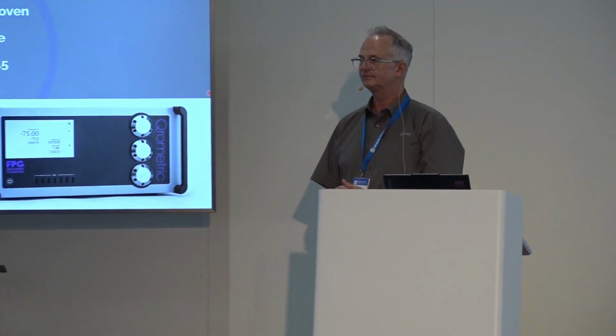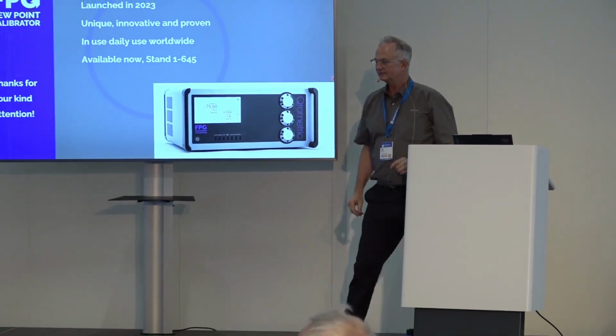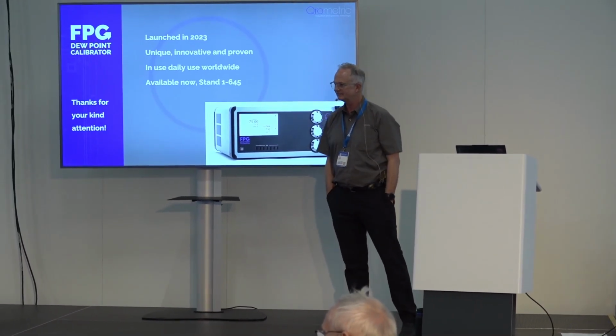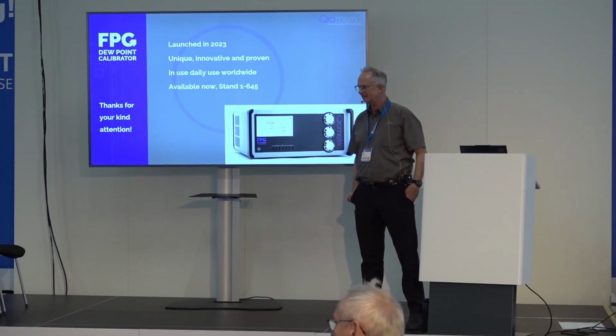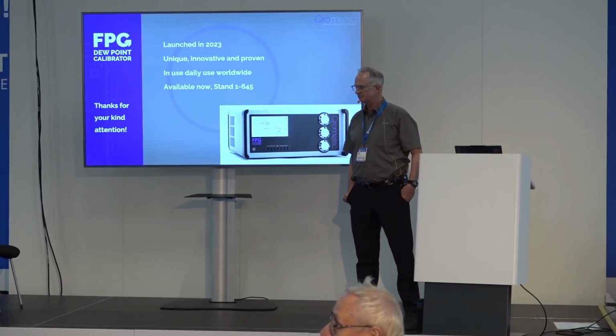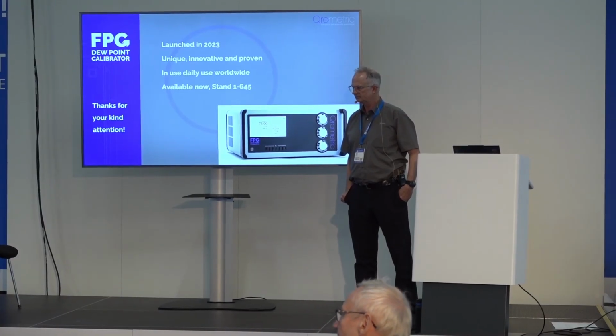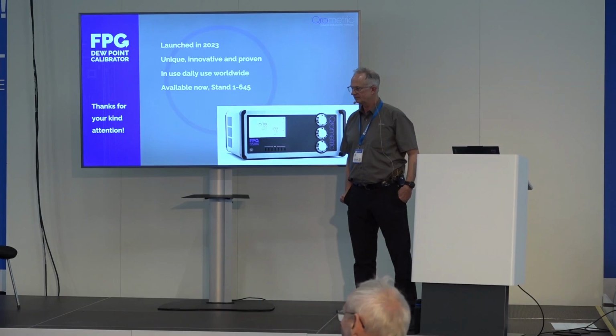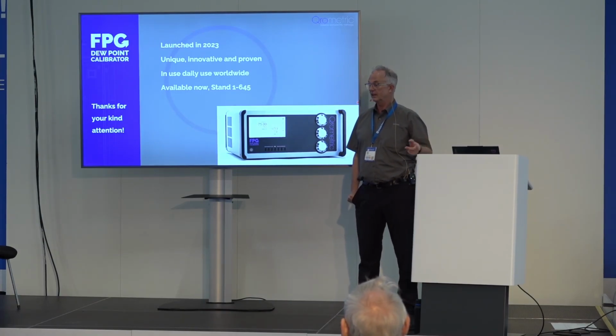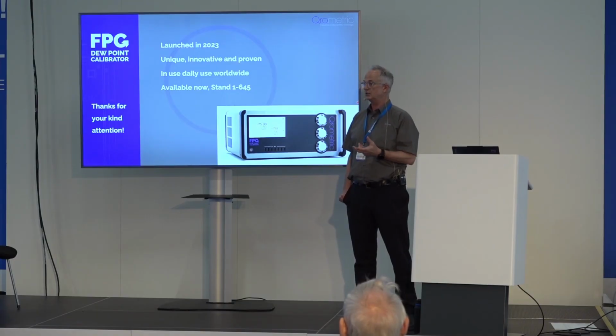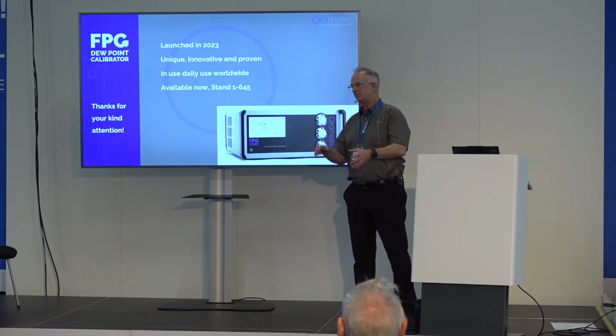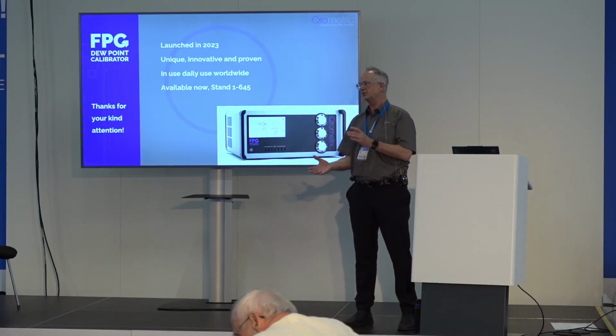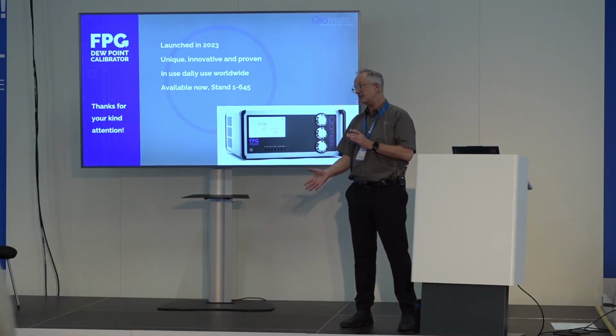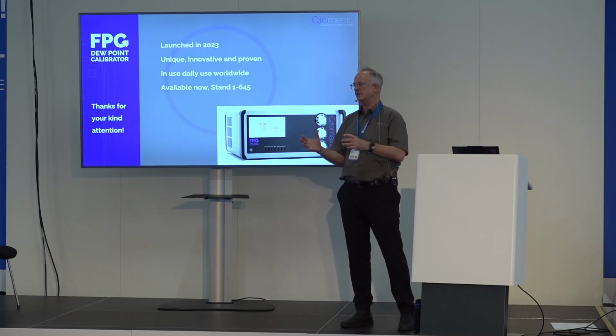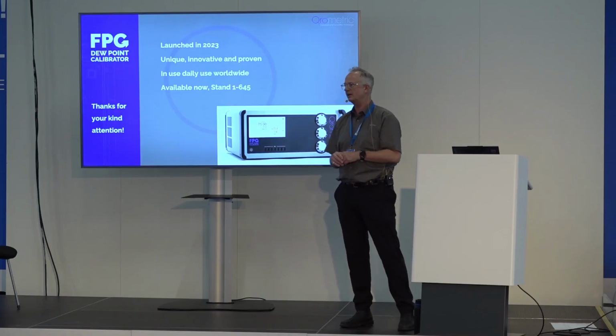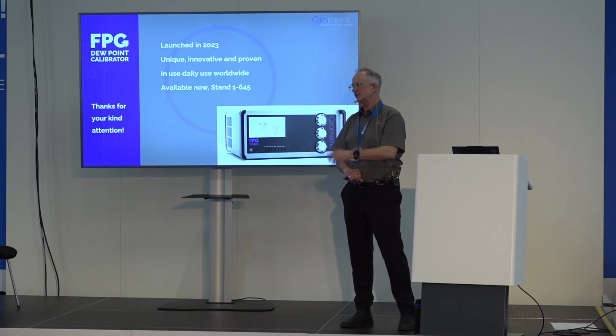So we have a question from Dr. Stefanelli. Yes, I have a question about the economic aspect. You told us that we save a lot of money if we calibrate our devices. How much does it cost to calibrate these devices? To calibrate the FPG? Yes. It would be around about the same cost as calibrating a dew point mirror or a reference standard. So, depending on your supplier, but typically around 2,000 euros every year or 2 years. Okay. So it's the same as having a calibration reference instrument. You can calibrate it by comparison. So about 2,000 every 1 or 2 years. Okay. Thank you.